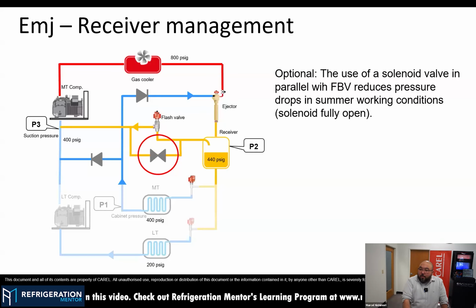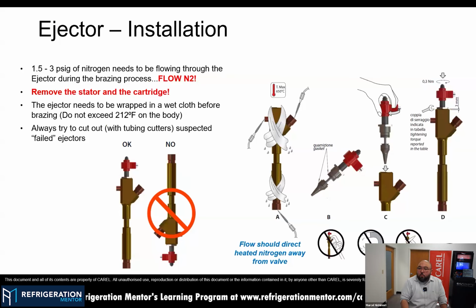So this is the overall introduction about the ejector, and let's talk about the installation. What should I take care of if I need to replace an ejector in the field? What precautions do I need to have? What are the main concerns? An ejector, from a mechanical perspective, is really similar to a valve. I was talking to R&D, I said, oh, okay, ejector is a valve. No, an ejector is not a valve, but for the sake of simplicity, we can consider that it's very similar to a valve on the mechanical installation.